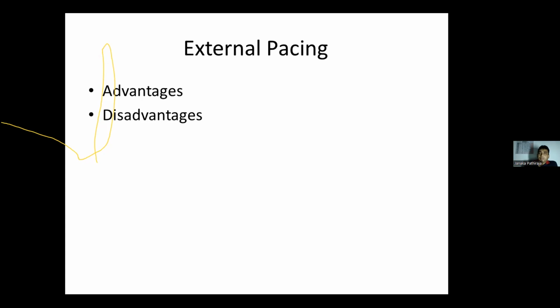They go and say, no, there is no external pacing machine. I asked the nurse or sister, there's nothing like that. So where is the external pacer? Is it a separate machine or with something else? It's in the monitor, sir. The defibrillator machine. It's an additional feature inbuilt in the defibrillator machine. We don't have external pacers as separate machines yet.